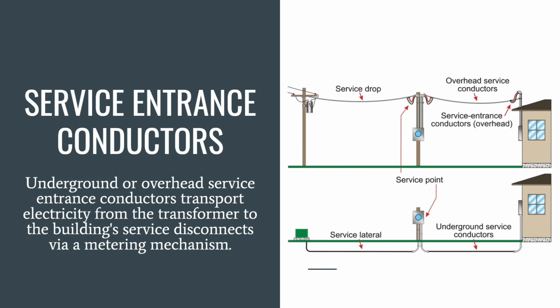Underground or overhead service entrance conductors transport electricity from the transformer to the building service disconnects via a metering mechanism or device. The service drop refers to the overhead cables that run from a pole-mounted distribution transformer to the building's service entry. The service lateral refers to the underground or buried service entrance conductors.